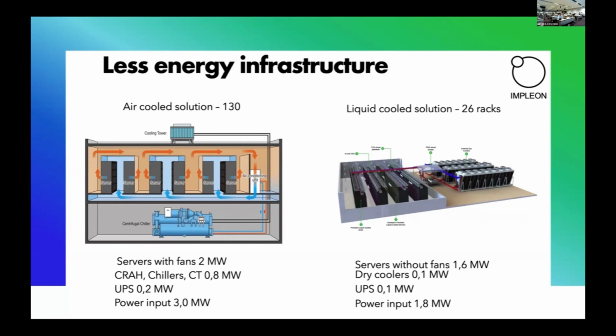This is why we don't need CRAH chillers or cooling towers, and this is why it's reduced from 0.8 megawatt to 0.1 megawatt. We have only dry coolers with the pumps. And uninterruptible power supply units are also reduced in energy consumption as well.